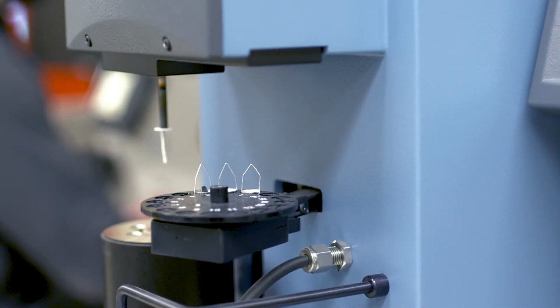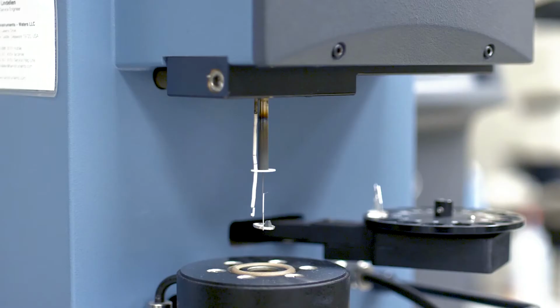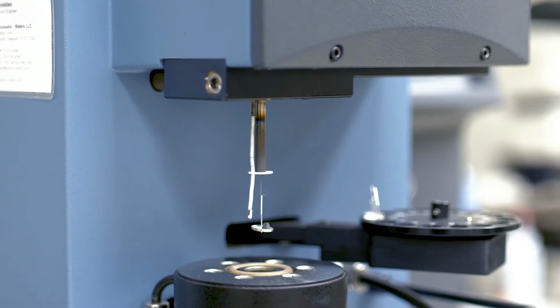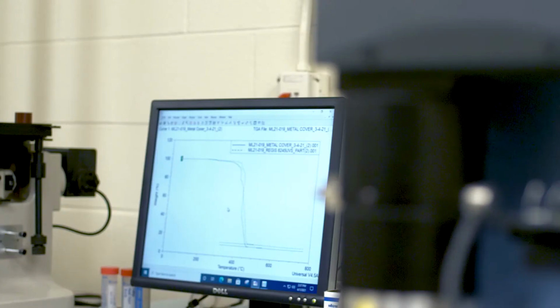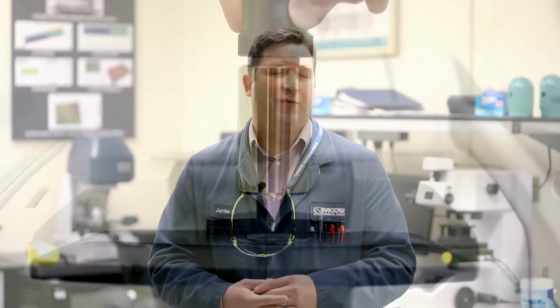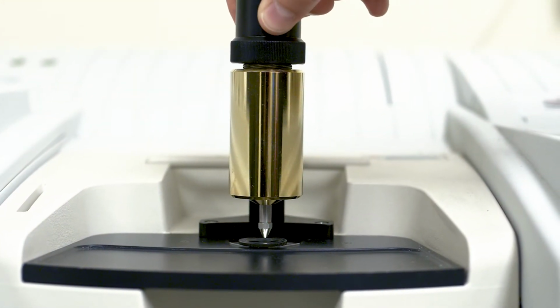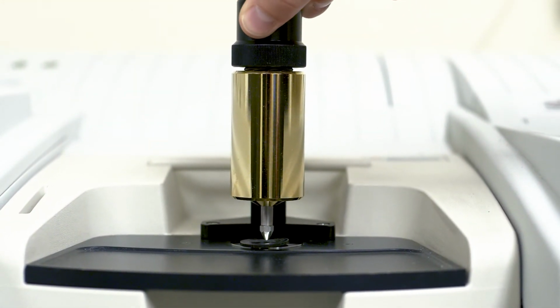In some of the other areas in the laboratory, we have a thermogravimetric analyzer that gives us the ability to look at what temperature different materials degrade at and what those decomposition components are that come off at different temperatures. We also have an infrared spectrometer that gives us the ability to get a molecular fingerprint on the materials that we use on the vehicle. So we can see if those materials have degraded over time from testing or due to use in service, or if a supplier has changed the material from what we had originally specified.